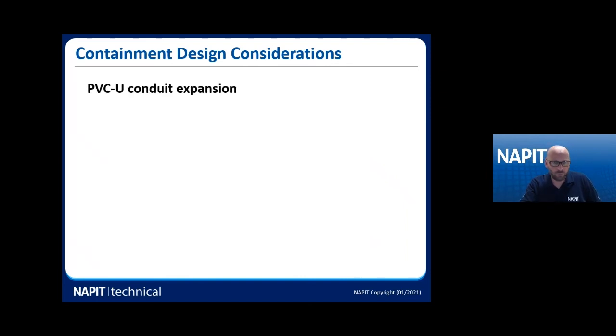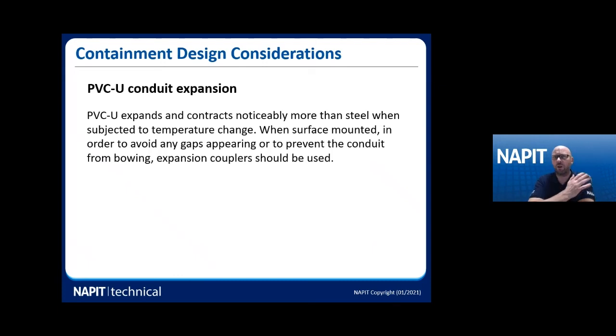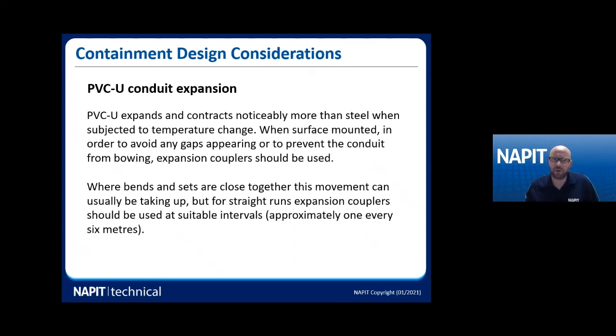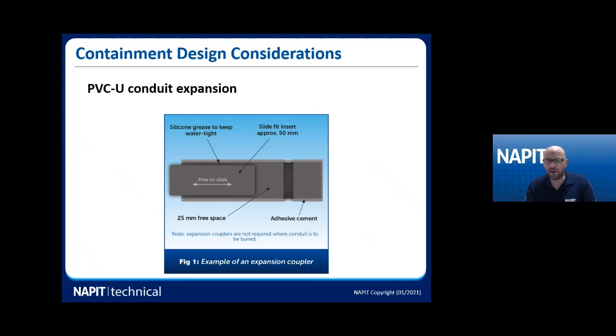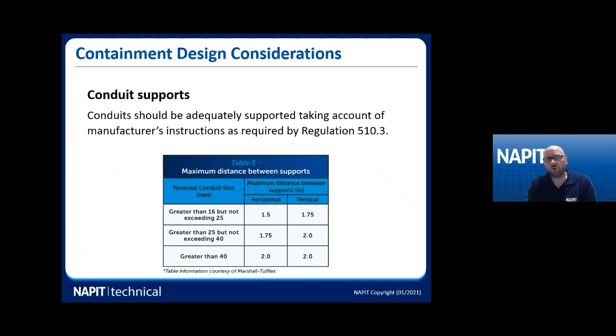When using PVC-U conduit, you need to think about how it expands, because it expands and contracts more noticeably than steel. When surface mounted, to avoid gaps or bowing you need to consider using expansion couplers — normally where you've got bends and sets close together the movement can be taken up in those areas, but for straight runs you should install expansion couplers approximately every six metres. You glue or cement one conduit into one side of the coupler and the other is free to slide — insert about 50mm and that will allow approximately 25mm of movement each way. In areas where water-tightness is needed, use silicone grease.